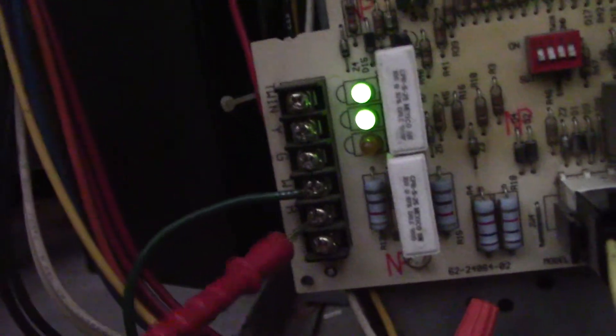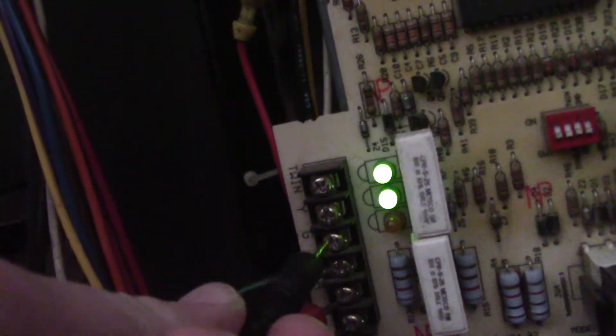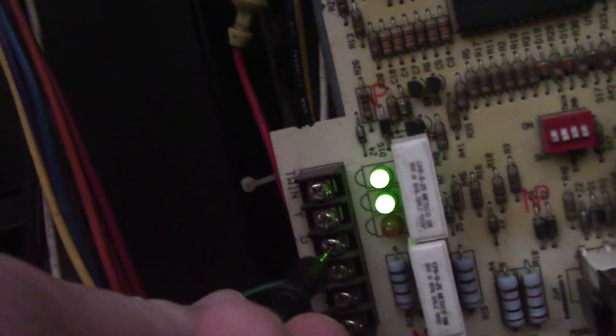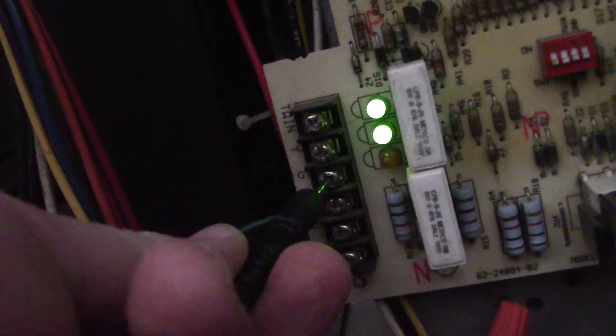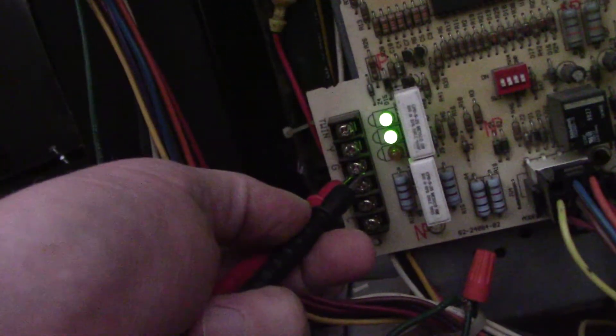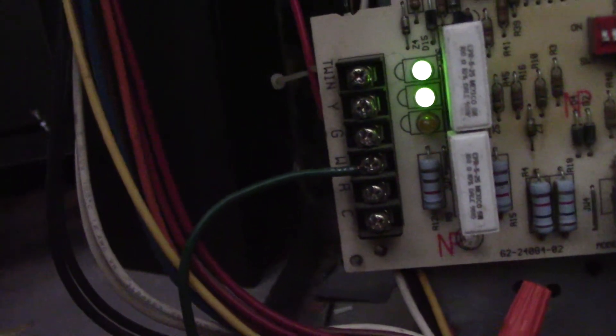If you go R and W and get zero volts, there's no potential difference because this is going to be the same as this, giving you a zero volt reading. In order to get a more accurate reading, you go from that W terminal right here, take it down to C, the 24 volt common terminal.